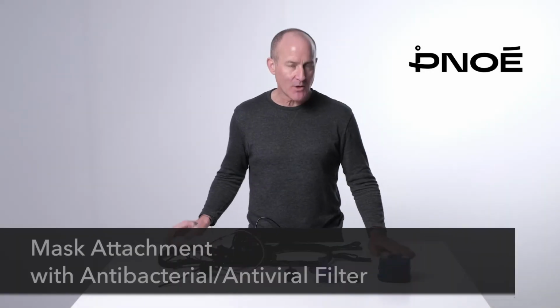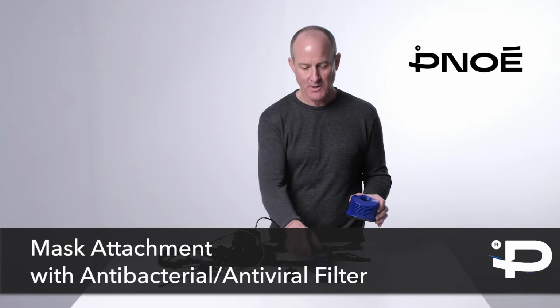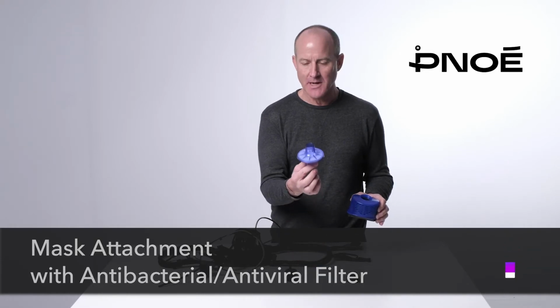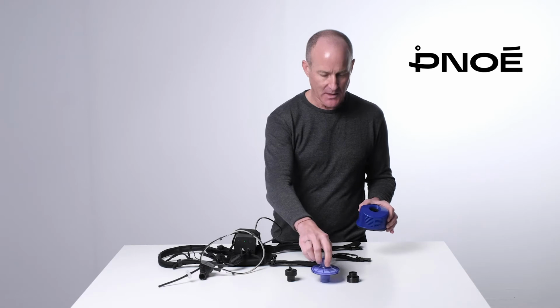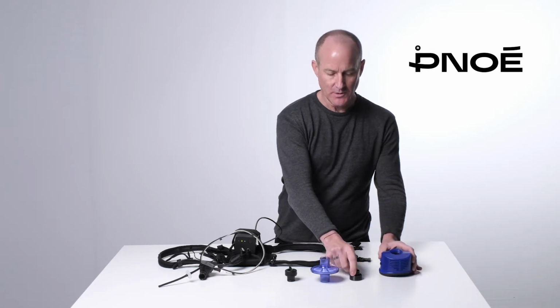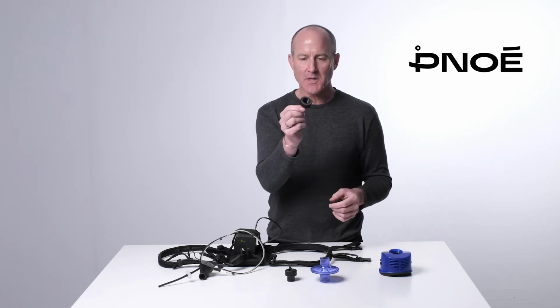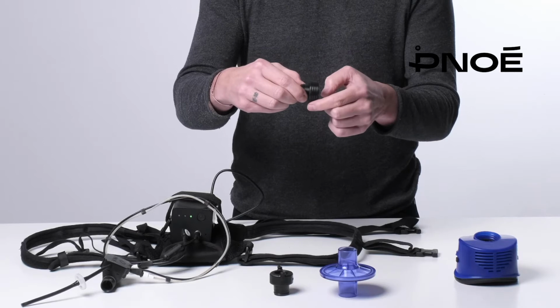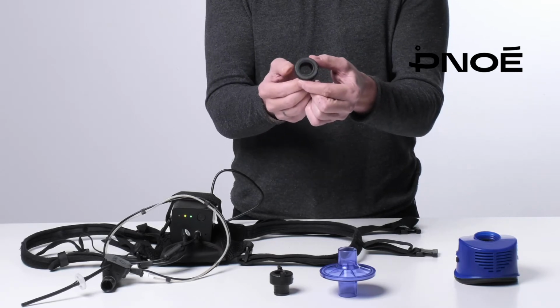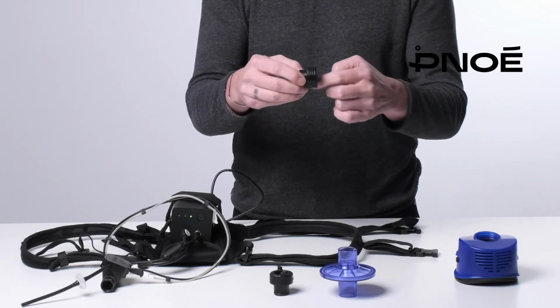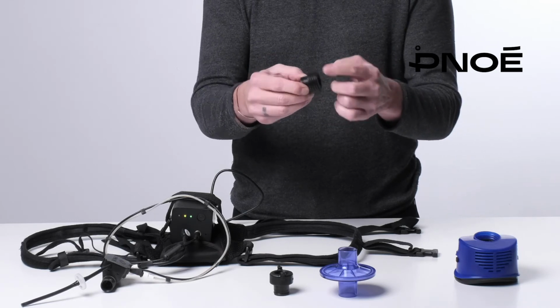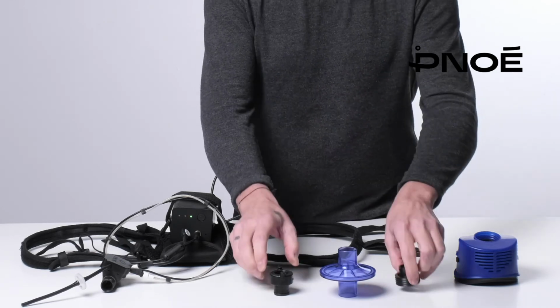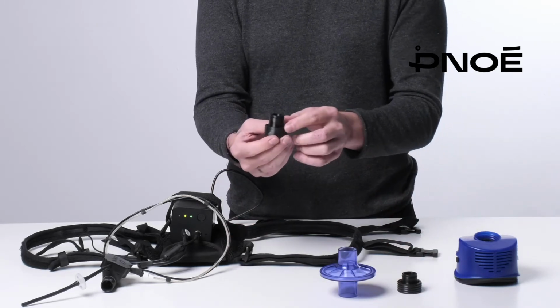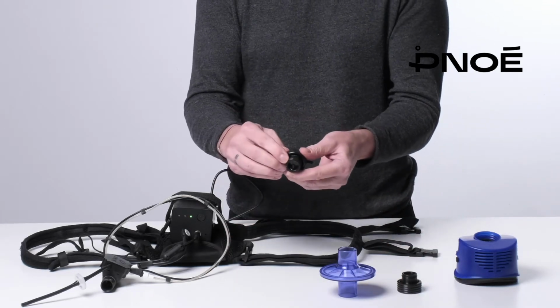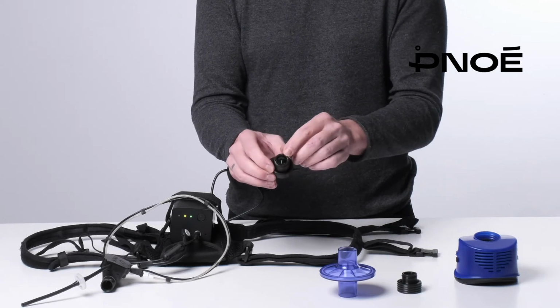So now we're going to show you how to hook up the mask when you're using an antibacterial and antiviral filter. You're going to need 2 adapters. Ensure you pick the right ones. The one that goes into the mask will have a screw and nothing down the center. So again, we'll have the rings for screwing into the mask and nothing down the center. And the adapter that goes into the filter will have a rubber ring and you'll notice the post in the middle.